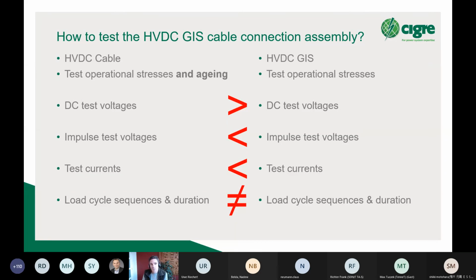So the question that we are trying to address in our working group is not to come up with new test requirements, but to actually find out which of those two different test procedures is more tough than the other one, and does it really cover all the stresses. And the idea here is to basically check if the cable tests, the PQ test and the type tests, are in principle sufficient to cover all of the stresses that are being exerted during an HVDC GIS test.